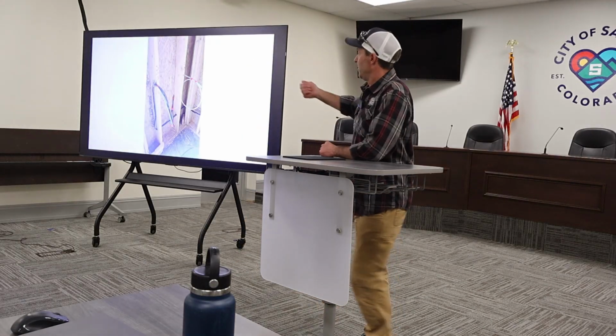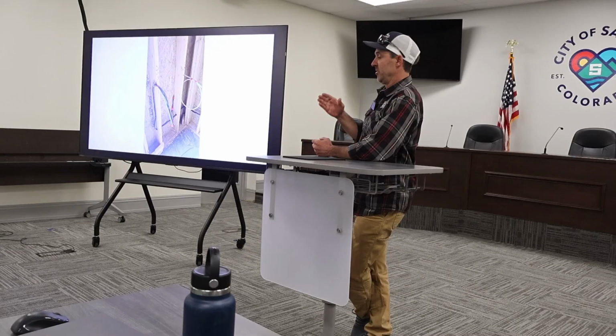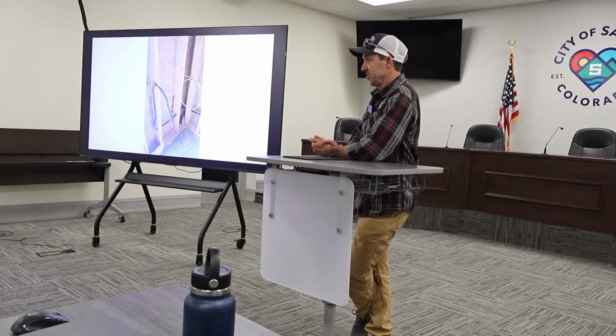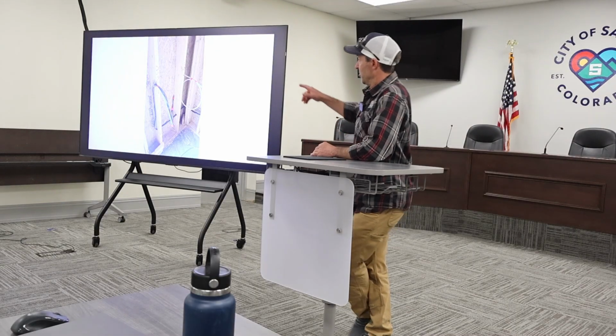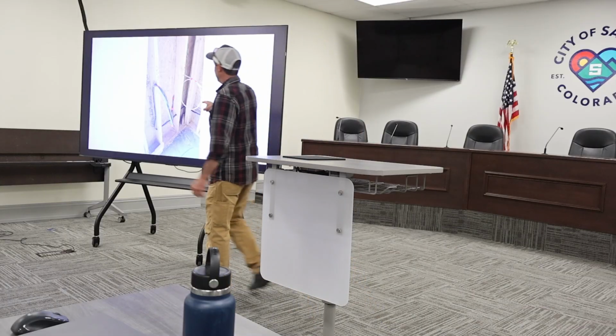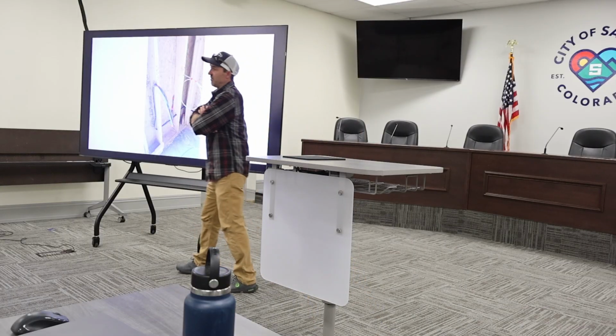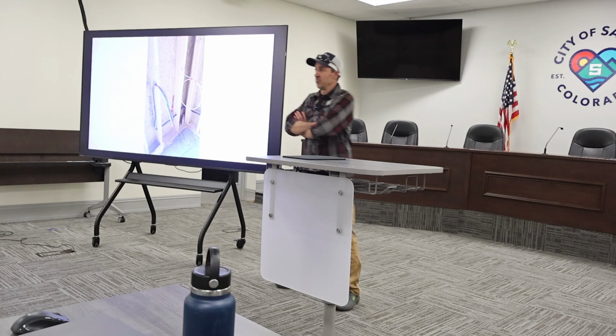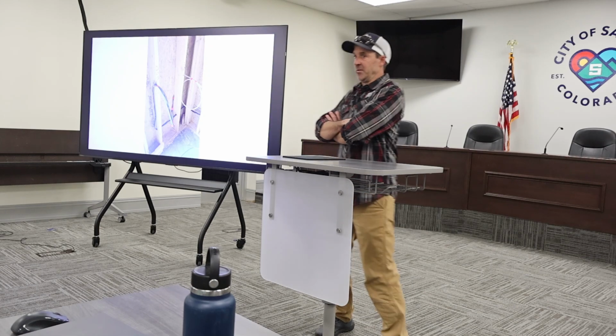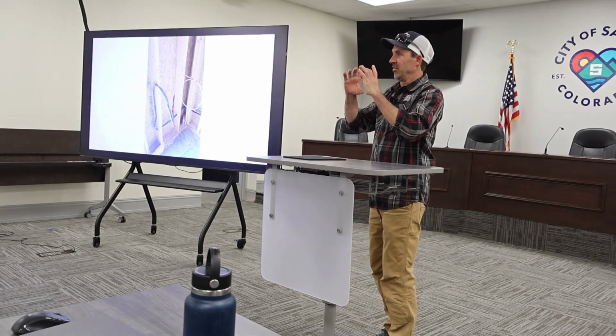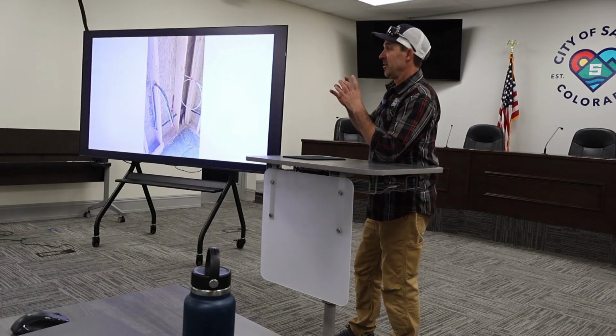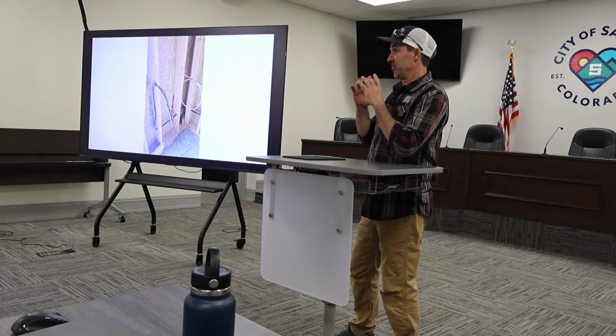The gray wire is the communication wire from the battery to the transfer switch. The brown one, also real important, is for the emergency stop switch, a push button disconnect any storage system has to have on the outside. You see them at gas stations, red and yellow, pretty ugly really, but no one wants that by their front door either.